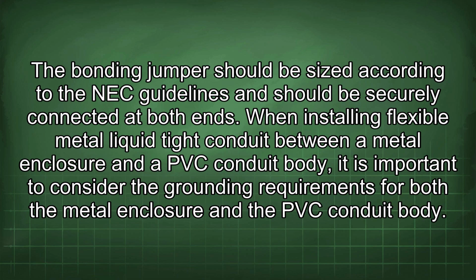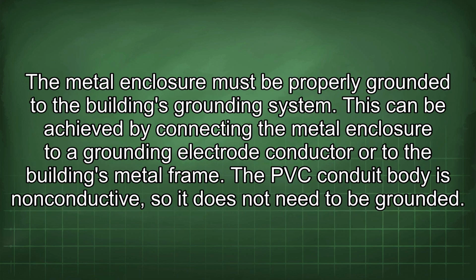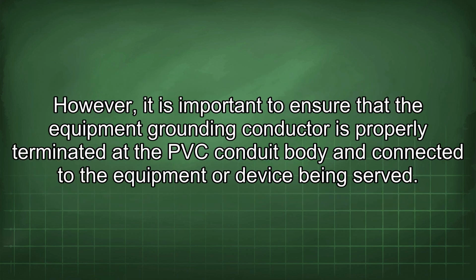When installing flexible metal liquid tight conduit between a metal enclosure and a PVC conduit body, it is important to consider the grounding requirements for both the metal enclosure and the PVC conduit body. The metal enclosure must be properly grounded to the building's grounding system. This can be achieved by connecting the metal enclosure to a grounding electrode conductor or to the building's metal frame. The PVC conduit body is non-conductive, so it does not need to be grounded. However, it is important to ensure that the equipment grounding conductor is properly terminated at the PVC conduit body and connected to the equipment or device being served.